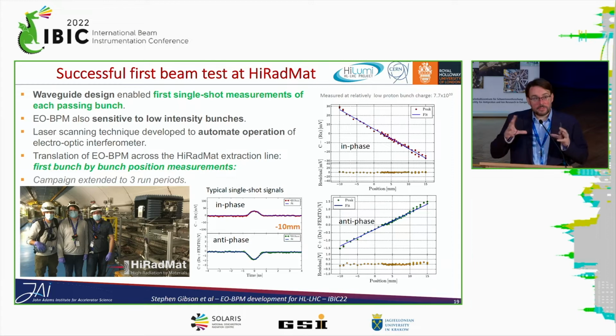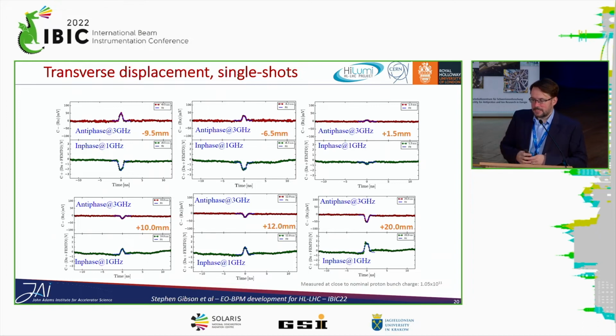The working point of the transfer function was set using an automated system where the laser makes a little frequency scan to assess where it is on the working point and then sets it to be at the optimum sensitivity position. So that was a useful part of the development. And the campaign was extended to several different runs. So as I said, this is for relatively low charge, and you see the in-phase and anti-phase signals. These are results for a slightly higher charge, closer to nominal. And as you translate the EO-BPM across the beam, you indeed see the anti-phase and in-phase signals basically shrinking or growing proportional to the distance across the beam.